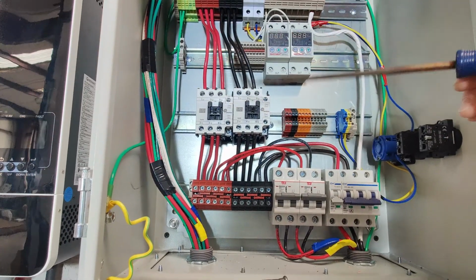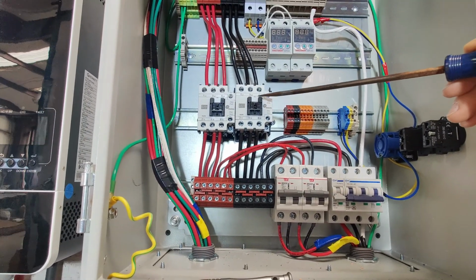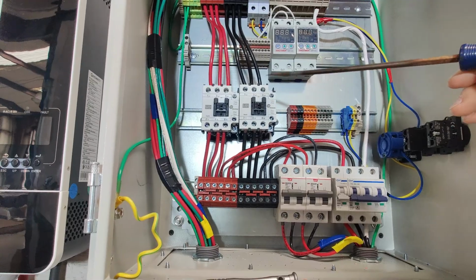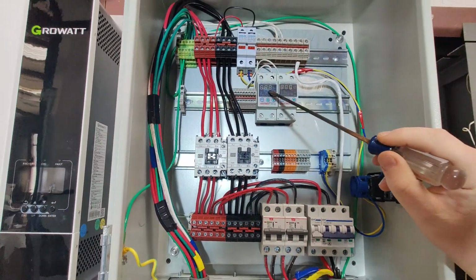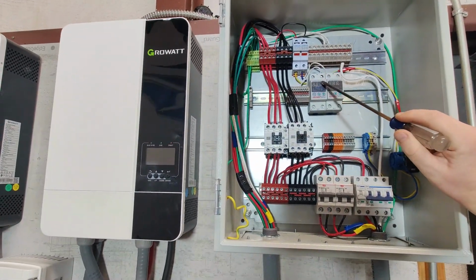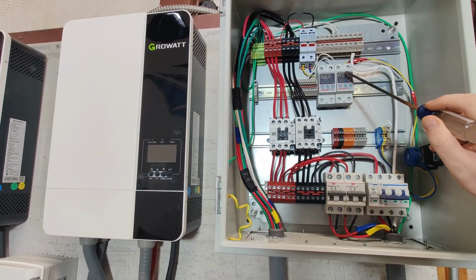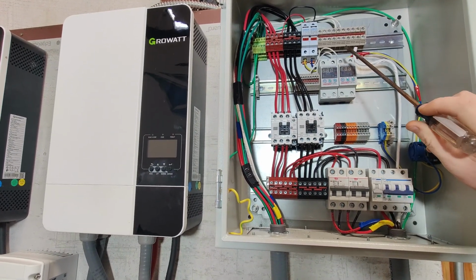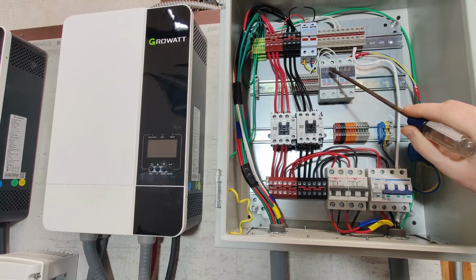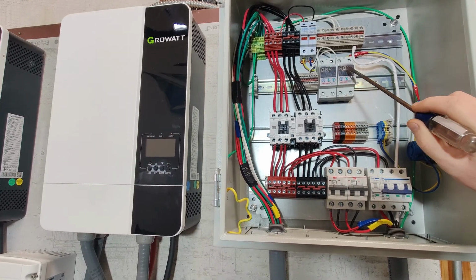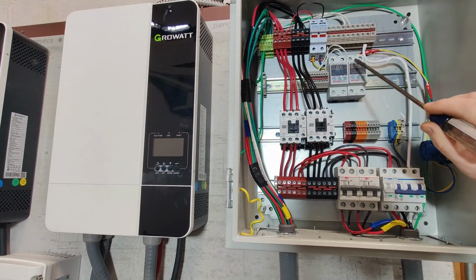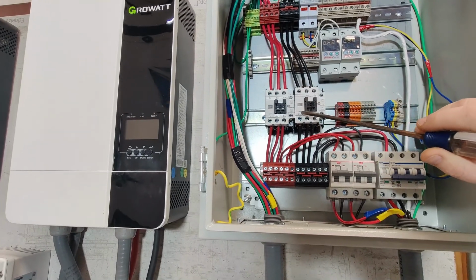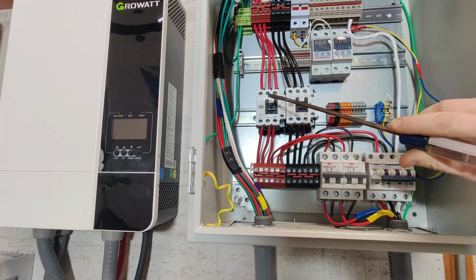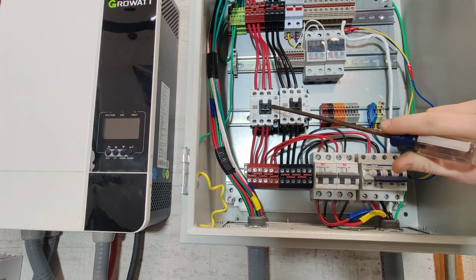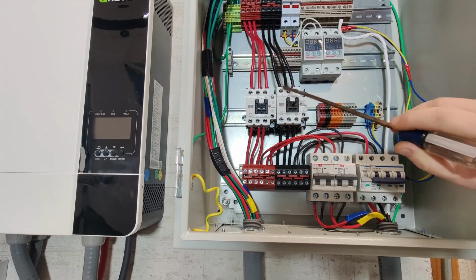I'm choosing to use 2 contactors this time around, because I'm going to monitor both legs of the circuit. The reason is I want the earliest possible detection of a failure. If there is a detection of a failure, we want to shut it down. You'll notice that these contactors are a little bit smaller than the ones we've been using. These are only 30 amp contactors, and we've got them wired in a little bit funny here.